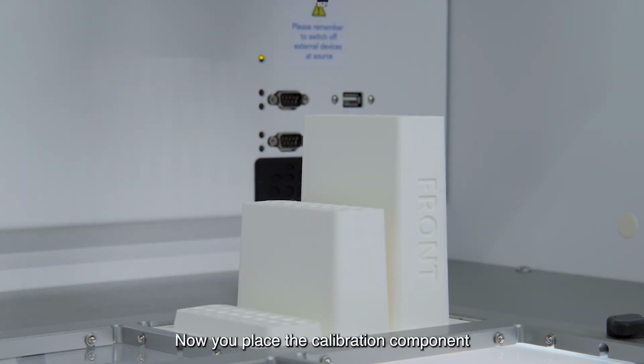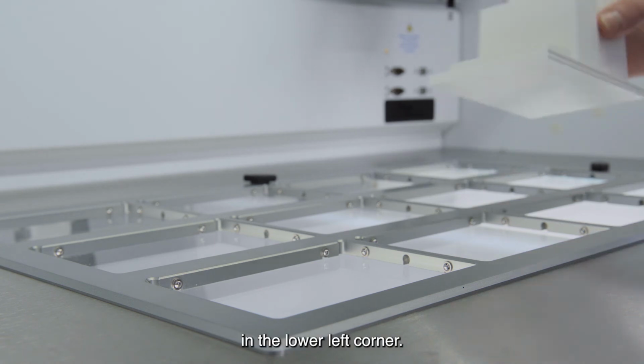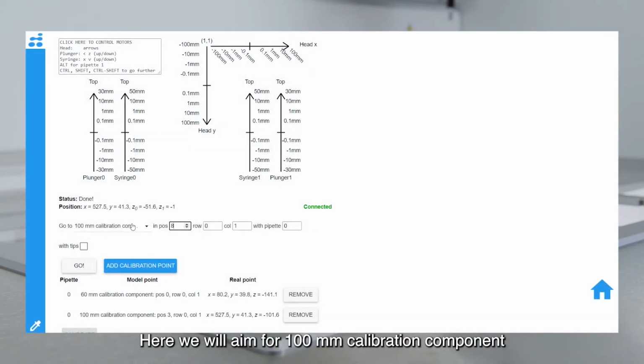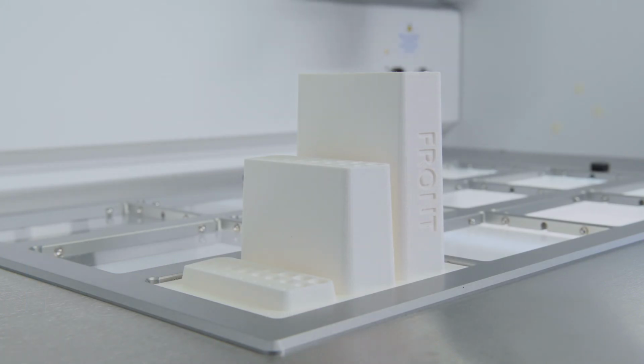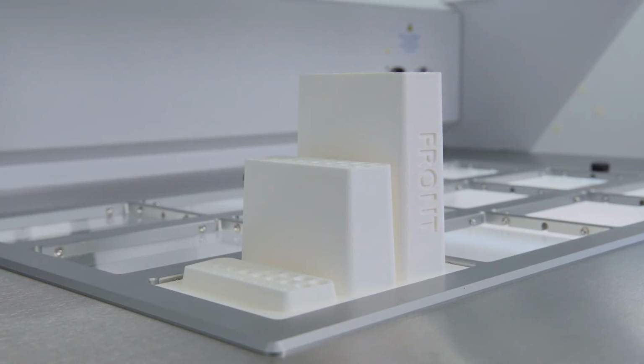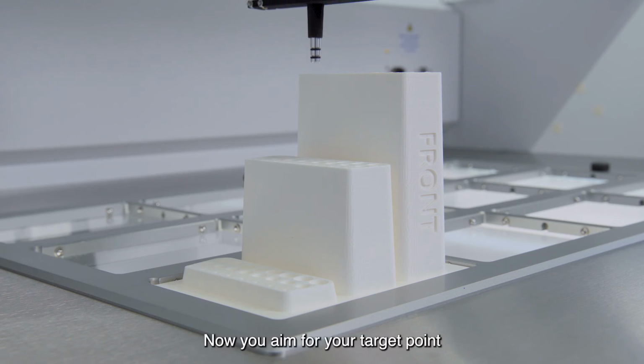Now you place the calibration component in position 8, which is the lower left corner. Here we will aim for the 100 millimeter calibration component as well, as it is important that the heights are the same diagonally. When you have placed the calibration component in position 8, you select go to 100 millimeter in position 8, row 0, column 1 with pipette 0 and without tips. And now you press go. Now you aim for your target point on this level just like before.